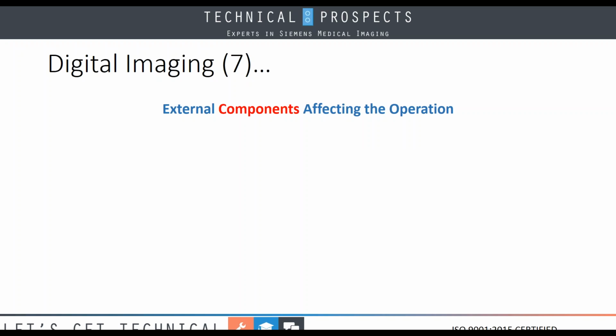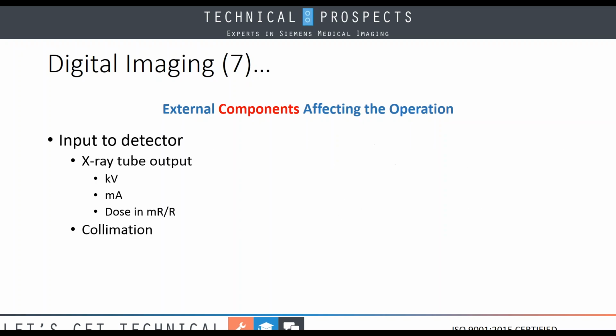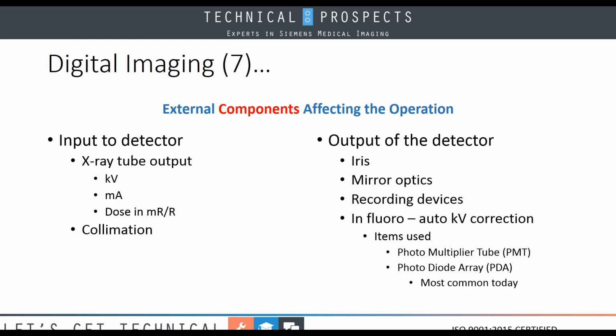Some external components that affect the operation. Okay, we have talked about this before. The input to the detector: the X-ray tube output, kV, mA, dose, in milliroentgens or roentgens. Is that all proper? Collimation. Are we properly collimating it down to get what we're looking for? And also removing scatter radiation, which will also destroy good image quality.